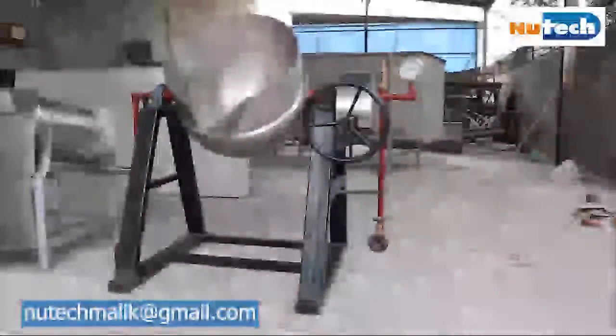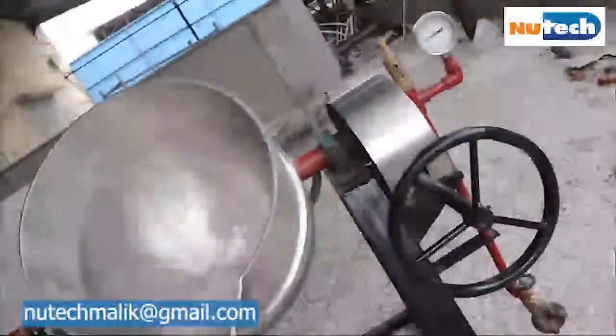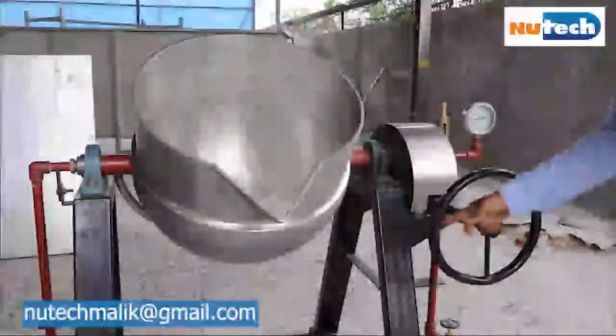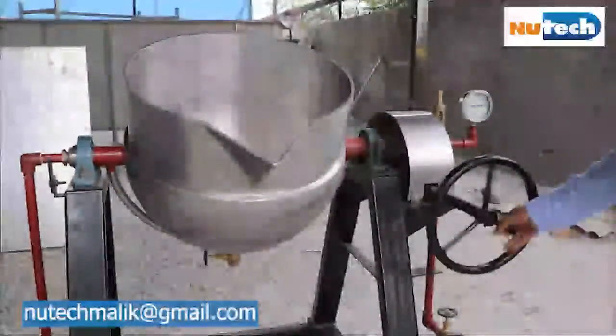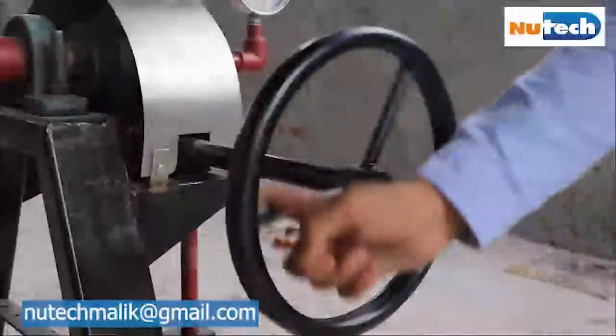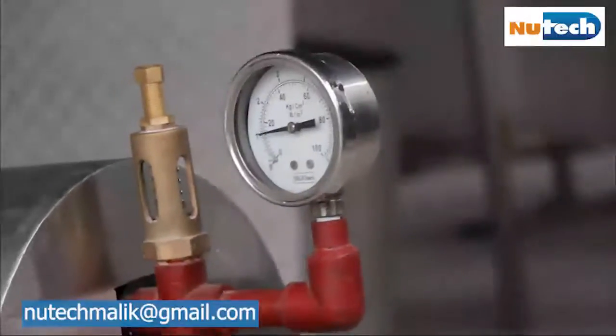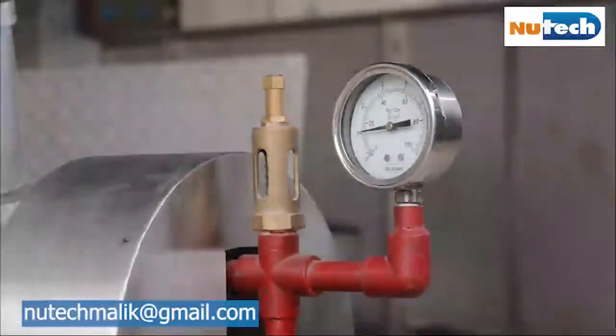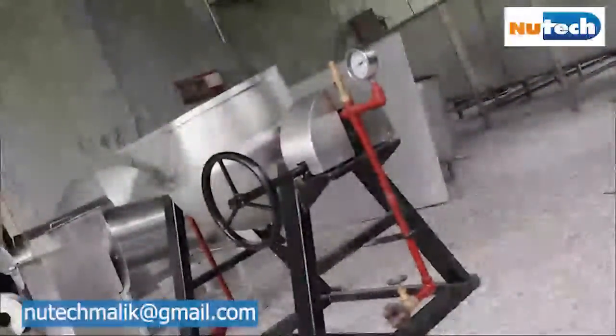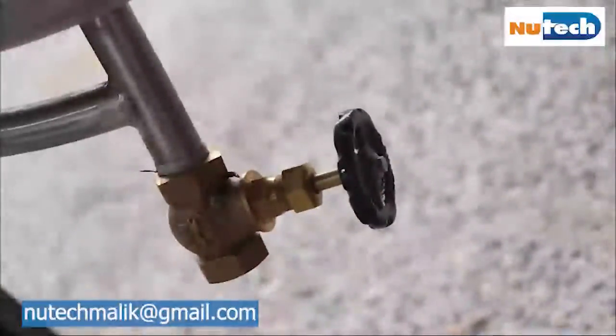The cooking kettle is a multi-purpose heating kettle fabricated from good grade stainless steel with a double jacket. The capacity of this kettle is 120 liters. It is steam operated and its motorized agitator is electrically driven. It is used for heating, making, and preparation of a wide range of products. The steam required is generated by a non-IBR 100 kg steam boiler at 6 kg per cm square pressure, with a wood fired boiler capacity of 125 kg per hour.